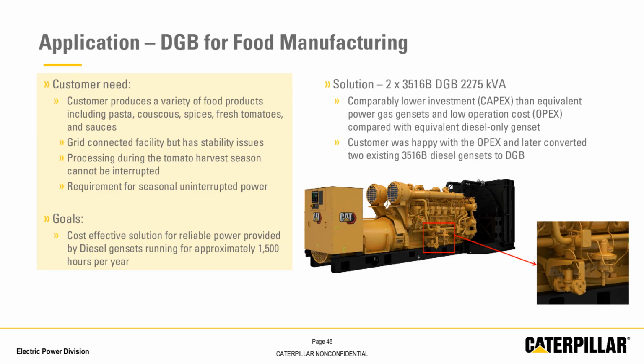So they ended up purchasing 2 DGB units, providing 2,275 kVA each. The benefits being lower capital investment than gas and low operation costs by running on the blend of diesel and gas, and also the resilience of being able to run on 100% diesel if required. The customer was very happy with the performance and low OPEX benefits of DGB, so they decided to retrofit their existing 3516B diesel units that they had already installed, and converted those to DGB as well.